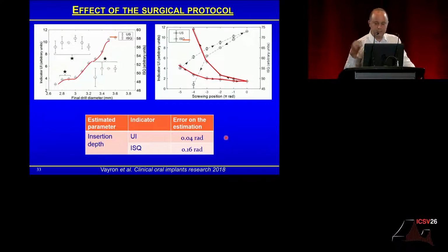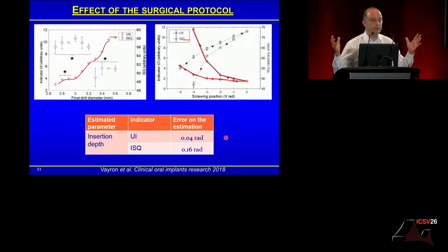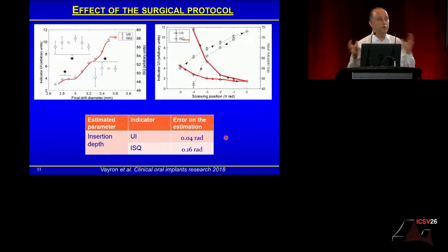These results are consistent because when you use ultrasound, and we could show that using numerical simulation, you are looking at what's going on, let's say, around 30 micrometers around the interface. Whereas when you use resonance frequency analysis, the vibration goes all over the test block or all over the bone. So you're not testing only the interface, you're testing the entire configuration, and that's why you have less sensitivity.